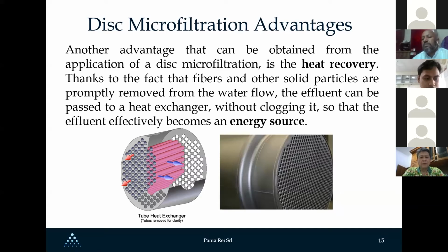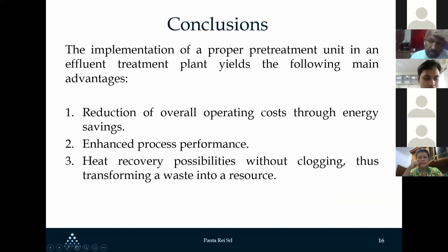This is not only about heat exchangers, because many of you also have cooling towers. If we put this kind of microfiltration before a cooling tower, we remove these fibers before they enter it, improving its operation and reducing the need for maintenance, since otherwise the fluff and fibers may clog the cooling tower. So this is another area of opportunity.